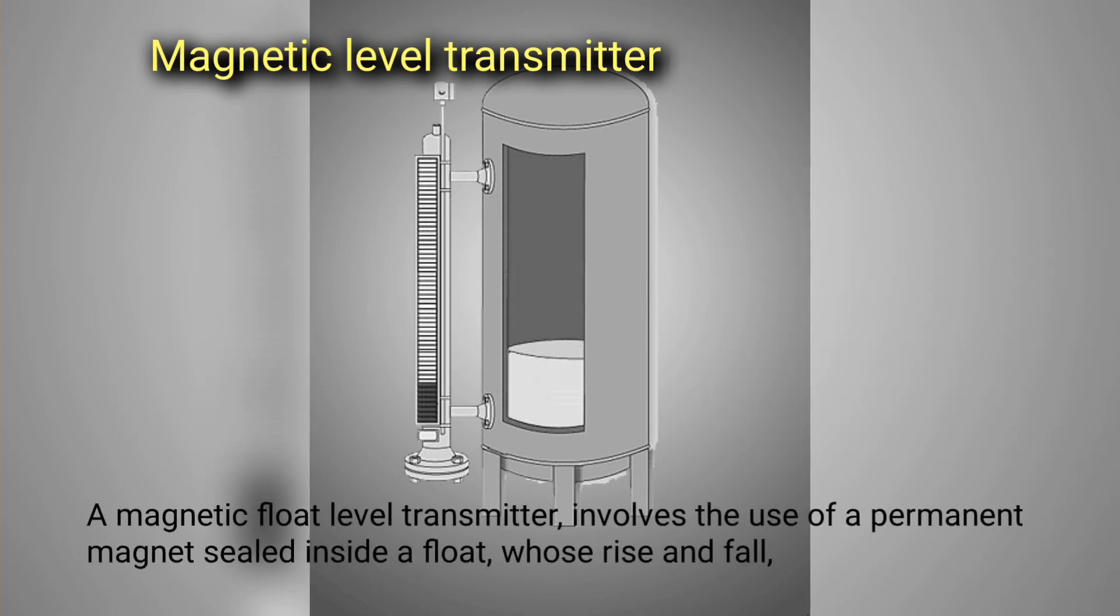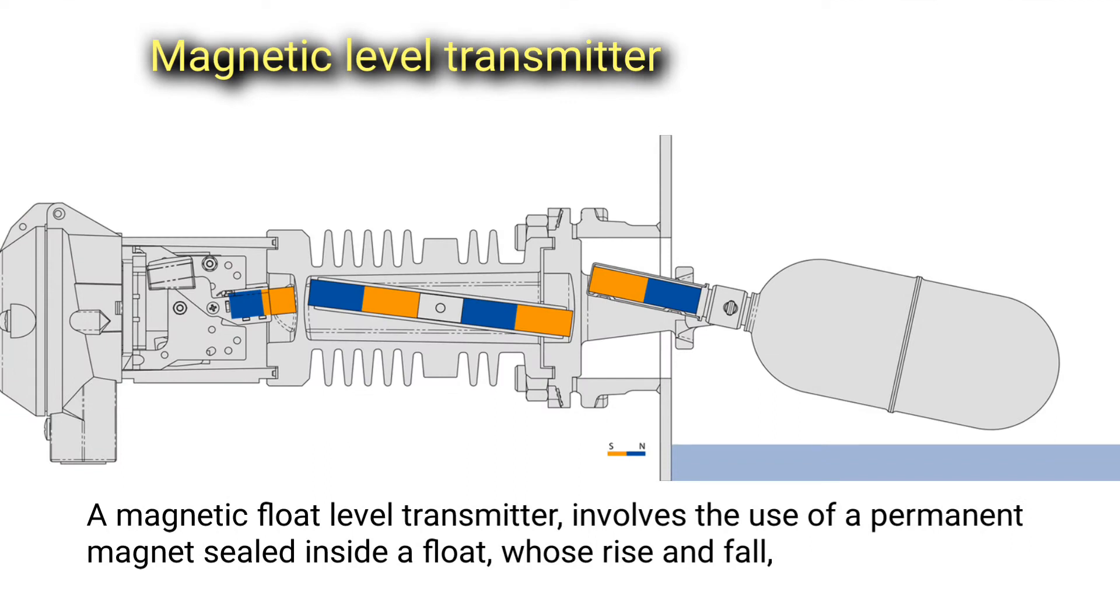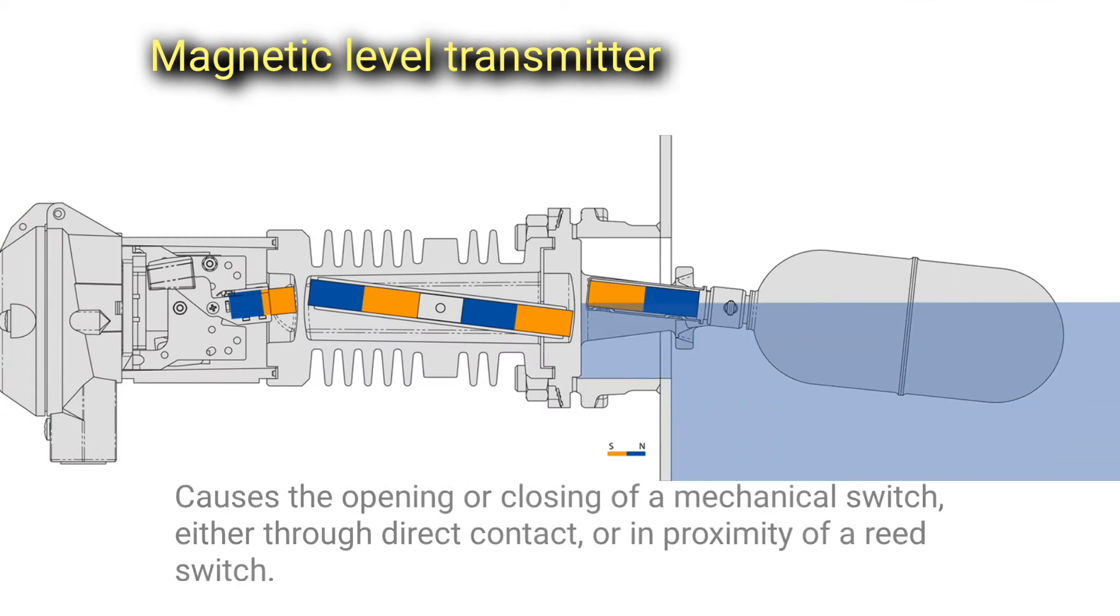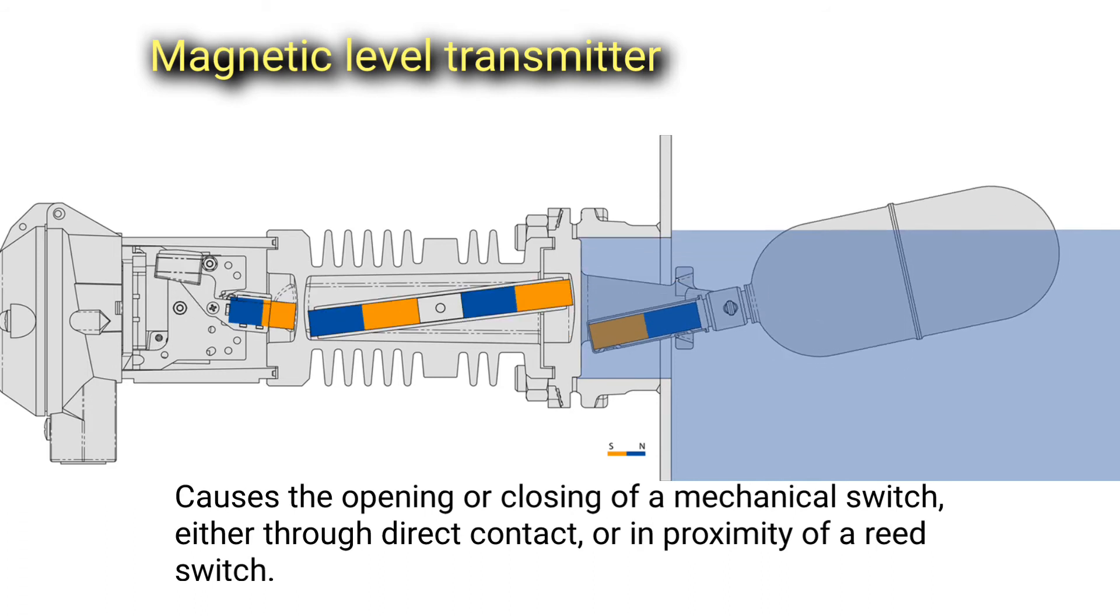A magnetic level transmitter involves the use of a permanent magnet sealed inside a float, whose rise and fall causes the opening or closing of a mechanical switch, either through direct contact or in proximity of a reed switch.